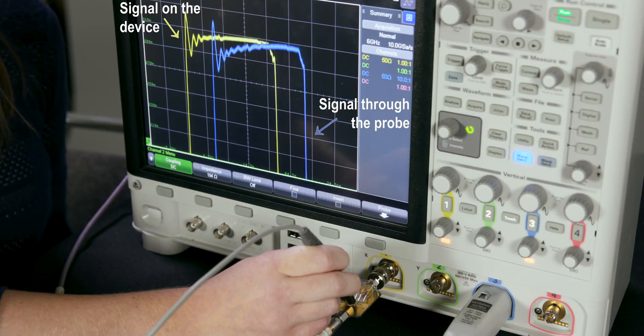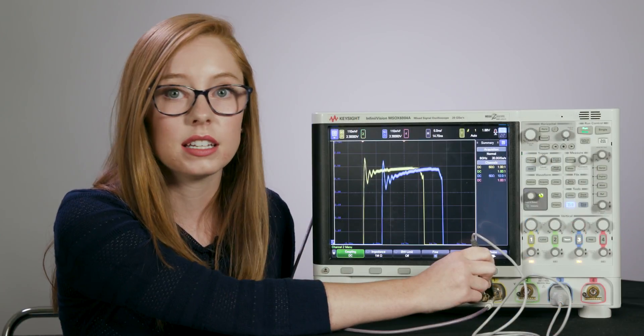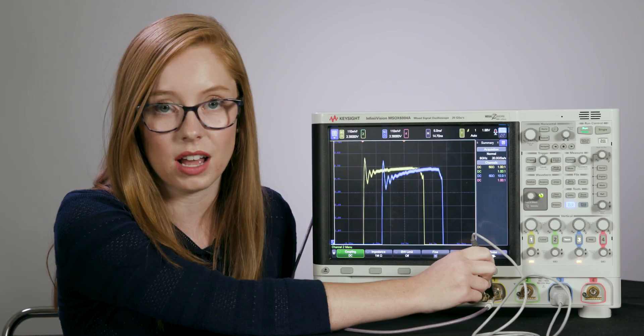And second, we can see that the blue trace looks almost identical to the yellow trace, which means that the signal you're seeing on screen is a true representation of the signal as it exists on your device. So why is there such a difference between a passive probe and an active probe?